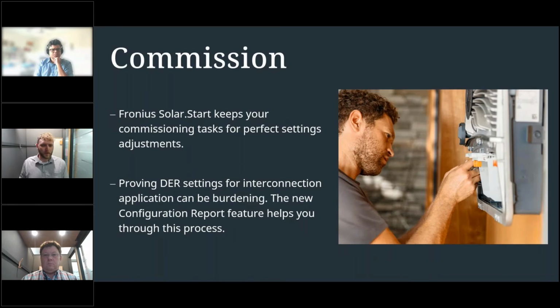We also understand that interconnection applications are time consuming and often frustrating. That's where the new configuration report feature comes in to streamline that process. Instead of taking screenshots of inverter settings and dealing with spreadsheets to send to utilities, the Gen24 now produces a file recognized by utilities that can be submitted to prove those DER settings are accurate and tied to that particular PV system. This really shapes up a new way of commissioning and going through the interconnection application.